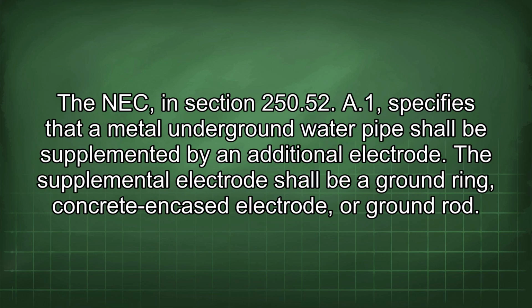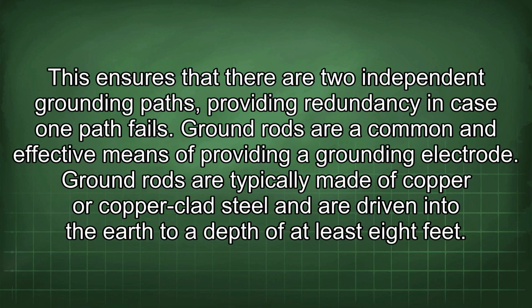The NEC in section 250.52(A)(1) specifies that a metal underground water pipe shall be supplemented by an additional electrode. The supplemental electrode shall be a ground ring, concrete encased electrode, or ground rod. This ensures that there are two independent grounding paths, providing redundancy in case one path fails.